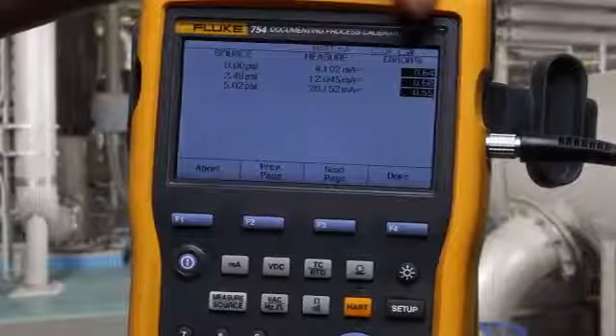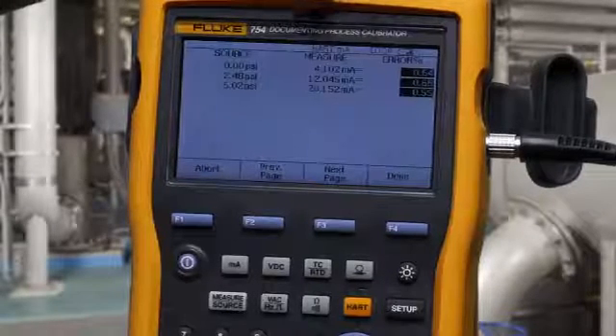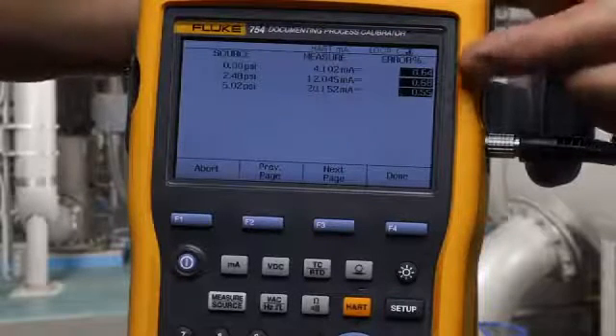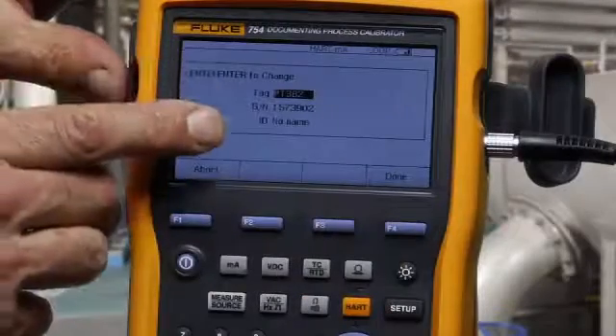If the found milliamp value deviates too far in value and the errors are greater than the test tolerance, they're flagged in a reverse video indication. Done. Tag, serial number, and who did the work. Done.